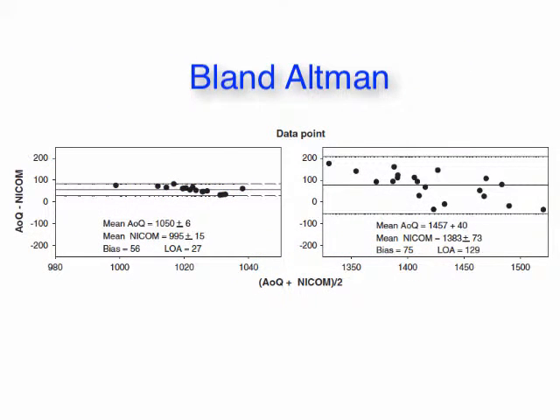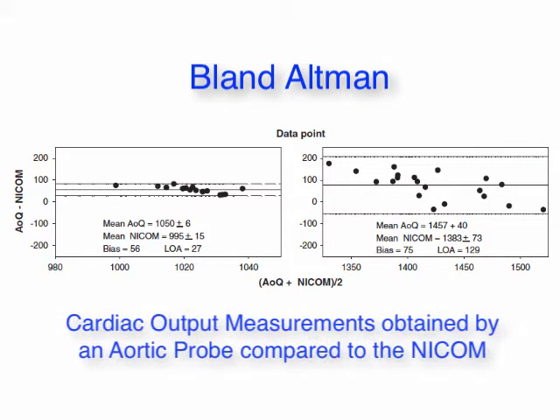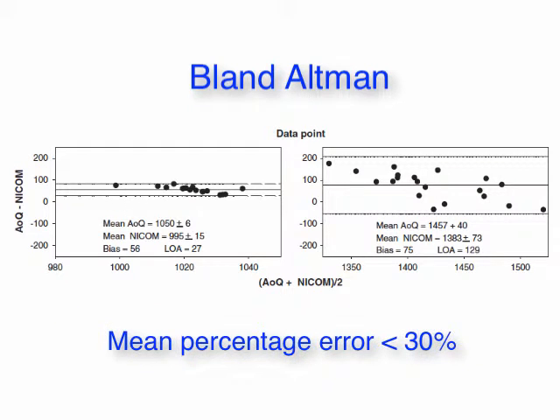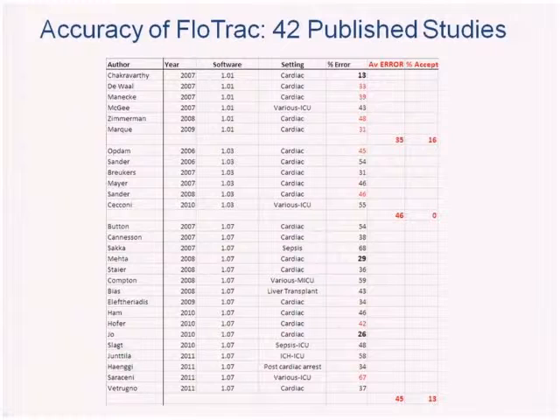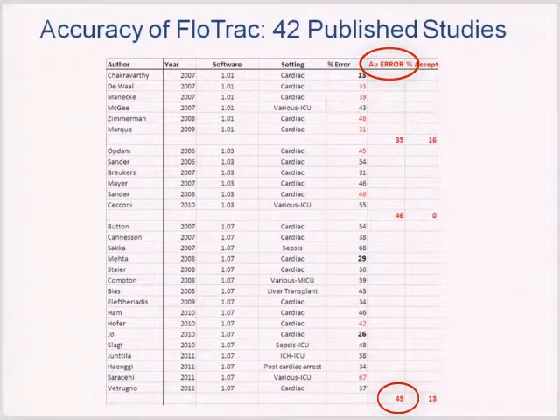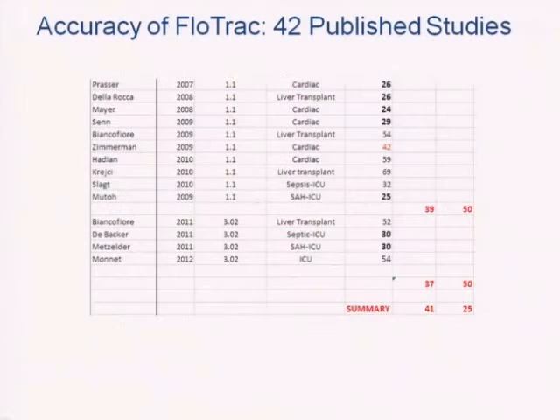As all monitors have inherent inaccuracies, the Bland-Altman method of analysis is recommended whenever comparing two technologies that are measuring a given parameter, such as the cardiac output. Ideally, the monitor should have a mean percentage error of less than 30% to be viewed as providing valid data. To put this in perspective, the FloTrac pulse contour cardiac output monitor produced by Edwards, and which has been widely adopted clinically, has repeatedly been shown to have an error between 40 to 45%.